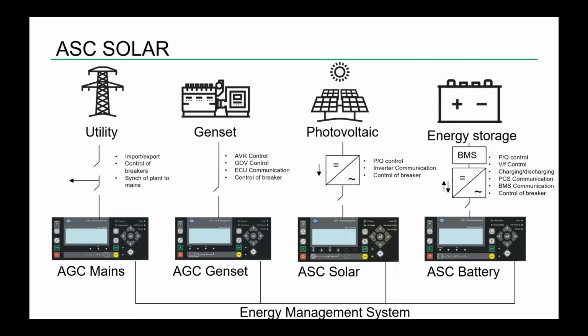And for the photovoltaic system, of course, the P/Q control is important with the inverter communication. Control of breaker. If you have a breaker there, we close the breaker from the ASC Solar side, and can of course also trip it. So as soon as the bus voltage is live, then we close the breaker, and now your inverters can reconnect to the system. And to complete the energy management system, we have the storage integration with the PCS communication and BMS communication on the right-hand side.